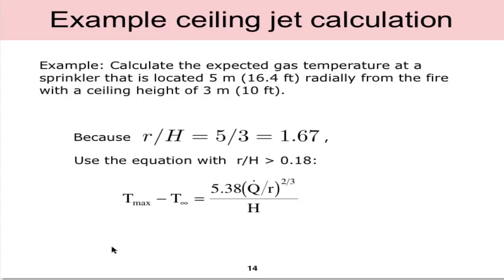Let's use that in an example. Here we're asked to calculate the expected gas temperature for a sprinkler that's located five meters radially away from the fire in a room with a ceiling height of three meters. Because r over h equals five over three, that ratio is 1.67, we should use the equation where r over h is greater than 0.18 and that's this equation here.